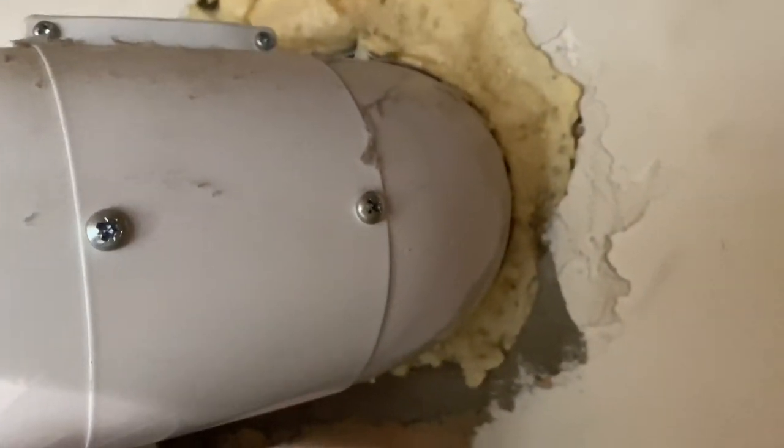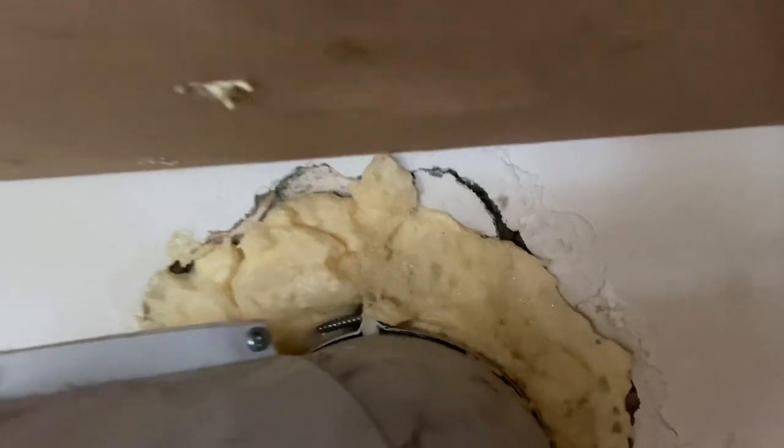If we have a look at the flue, it's been filled with expanding foam but the joint is in the wall — the actual flue joint is in the wall. I haven't been out to any of these jobs so I'm just relying on the subscribers who sent them in. The Ideal Esprit just goes to show how the flue needs to be supported correctly and be secure. On the Vaillant, the gas should be installed correctly and sealed, and the flue joint again shouldn't be in the wall unless the manufacturers say something different. As always, read the manufacturers' instructions.